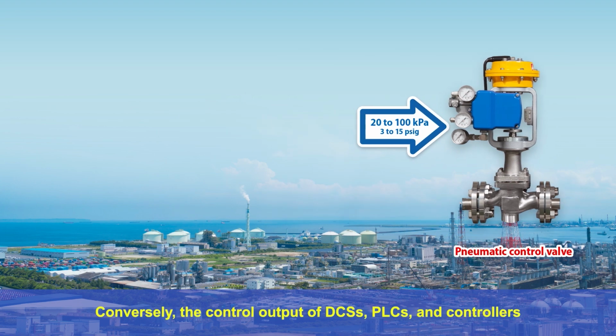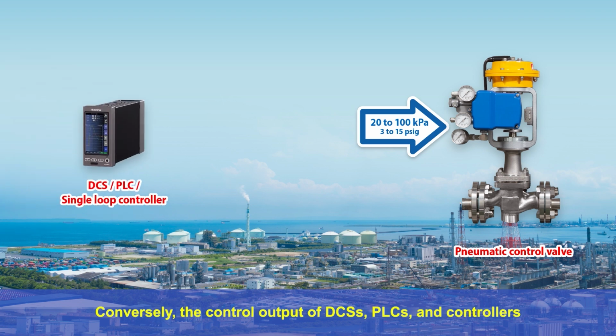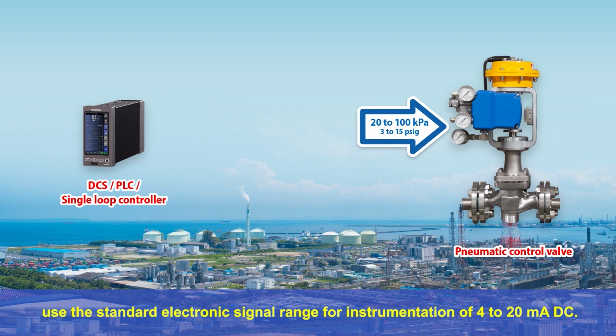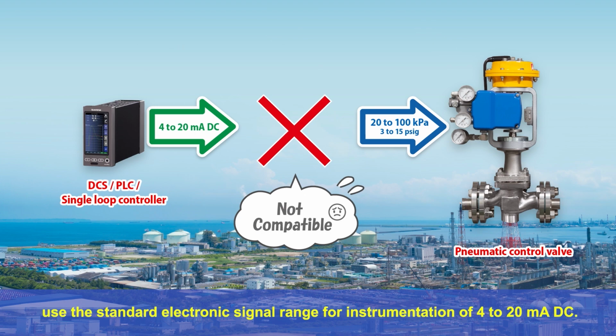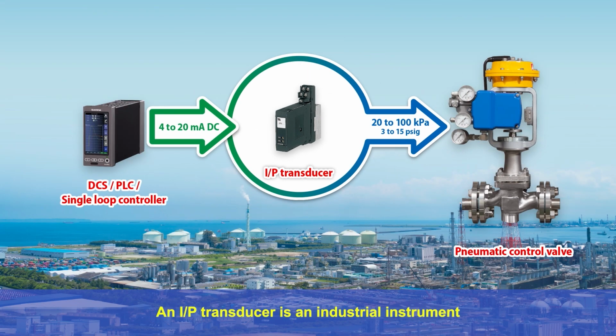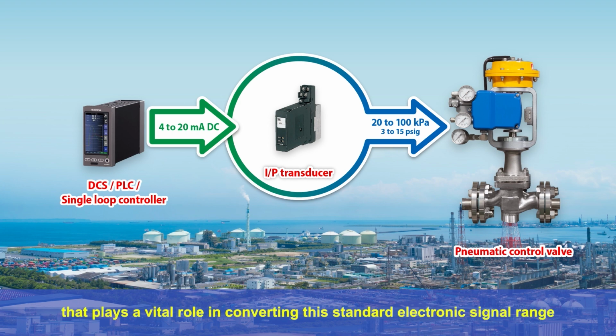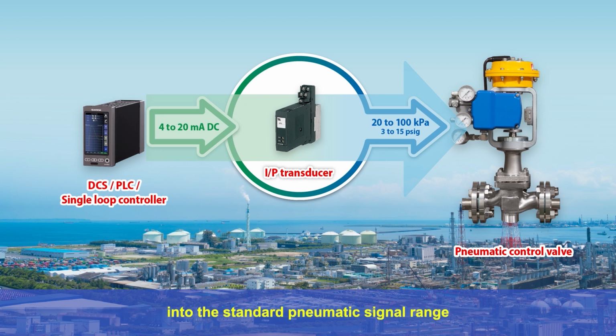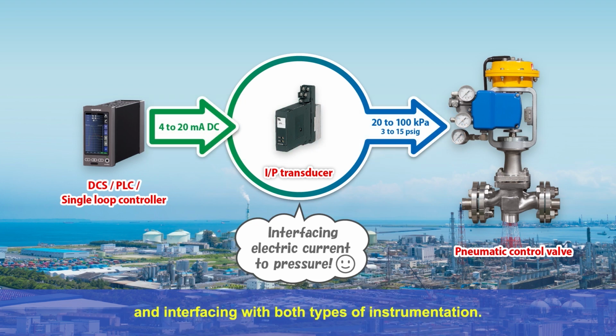Conversely, the control output of DCSs, PLCs, and controllers use the standard electronic signal range for instrumentation of 4 to 20 milliampere DC. An I-to-P transducer is an industrial instrument that plays a vital role in converting this standard electronic signal range into the standard pneumatic signal range and interfacing with both types of instrumentation.